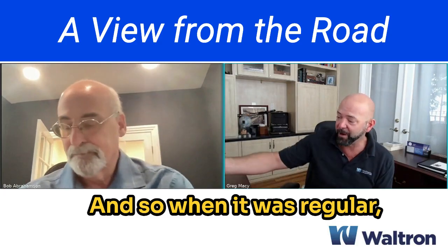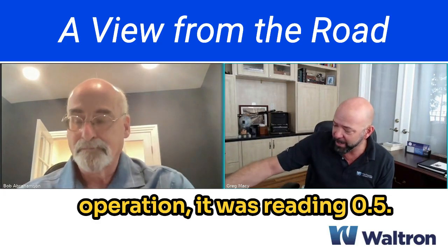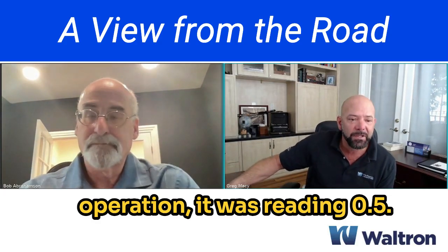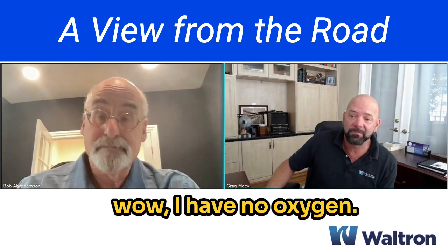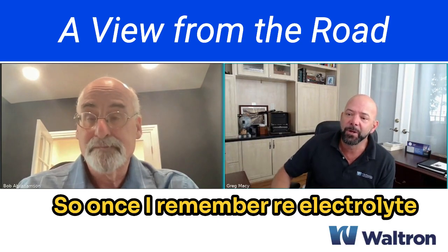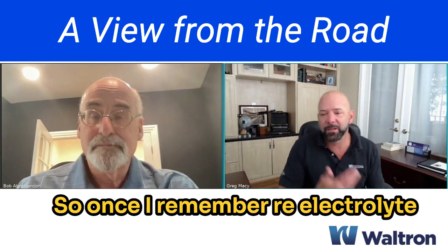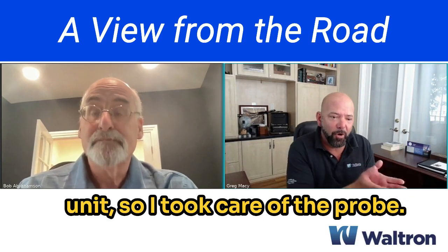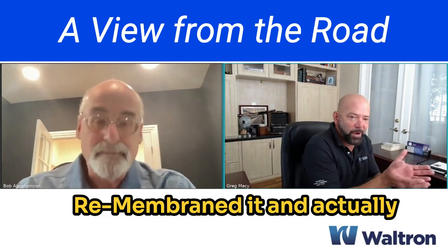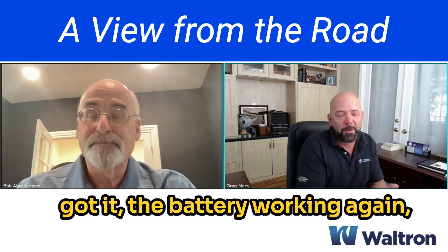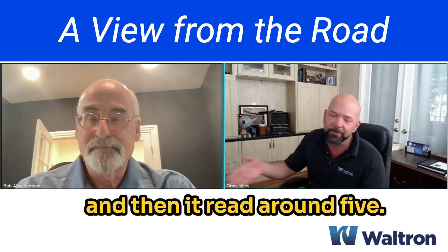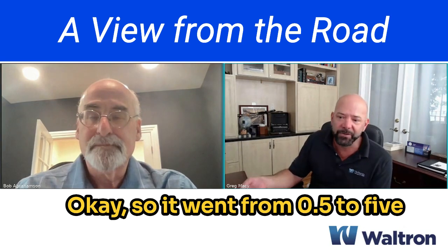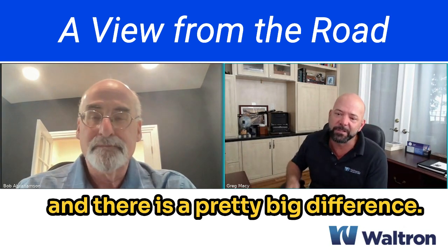When it was running in operation, it was reading 0.5. So the plant thought, wow, I have no oxygen. So I re-membraned, re-electrolyted, took care of the probe, got the battery working again, put it back in, let it rinse down, and then it read around 5. So from 5, and there's a pretty big difference.